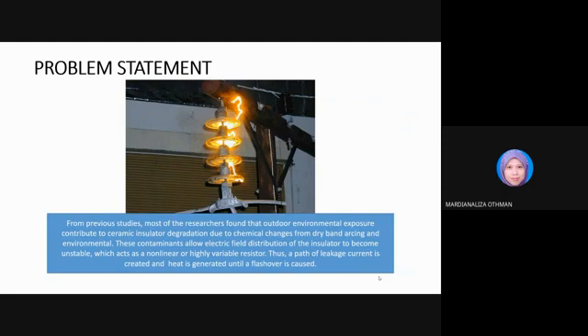For the problem statement, from previous studies, most researchers found that outdoor environmental exposure contributes to ceramic insulator degradation due to chemical change from dry band arcing and the environment. This contaminant allows the electric field distribution of the insulator to become unstable, acting as a non-linear or highly variable resistor. Thus, a path of leakage current is created and heat is generated until a flashover is caused.